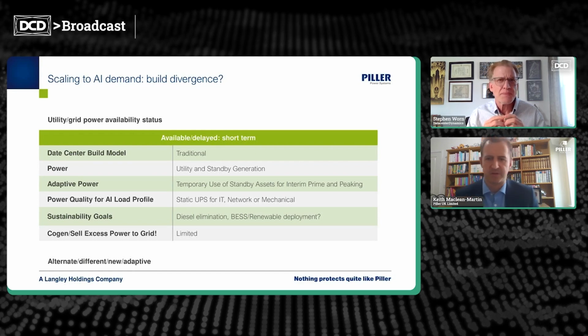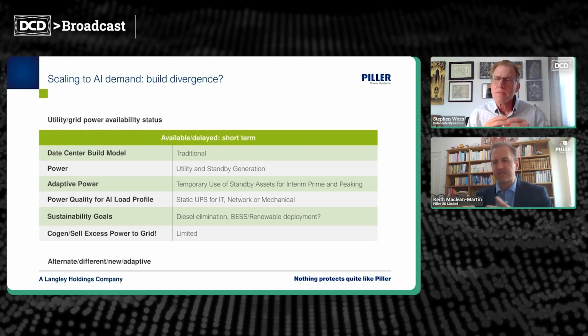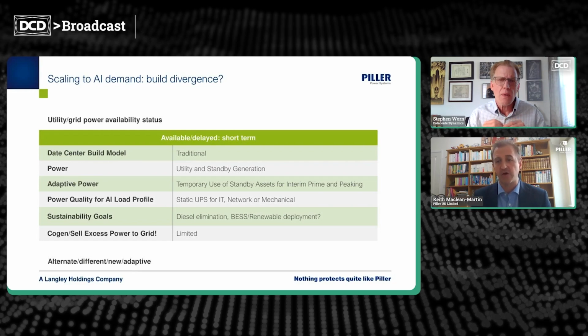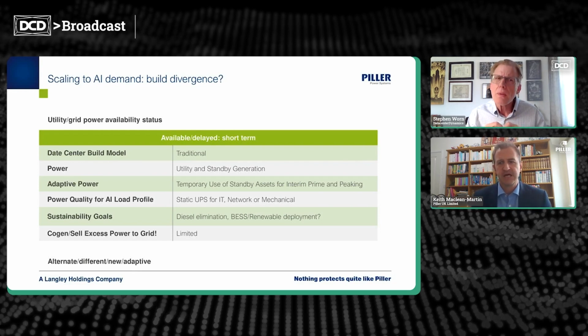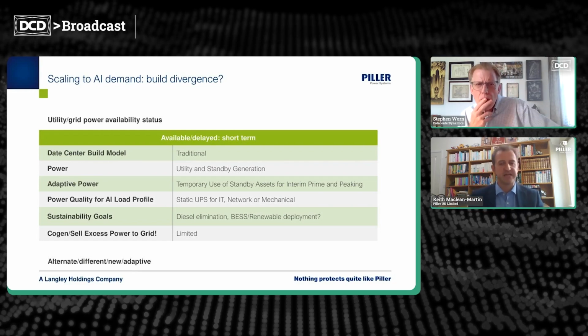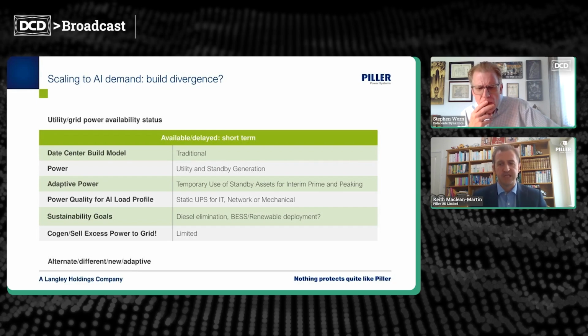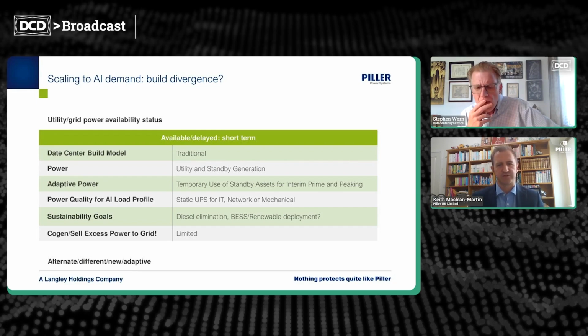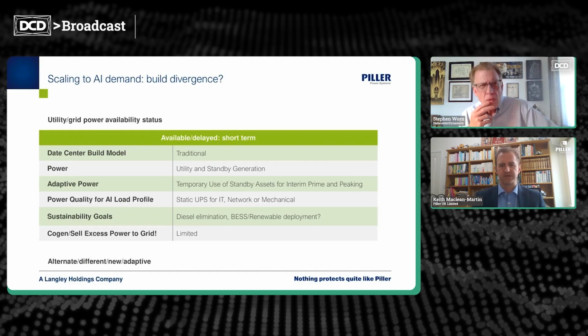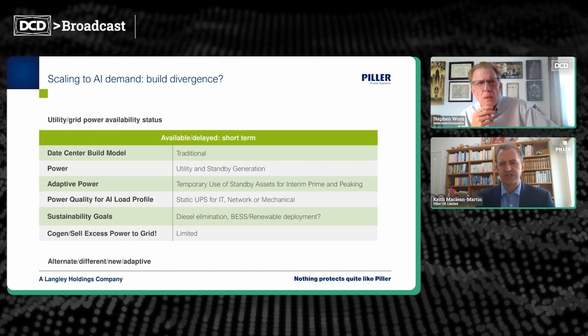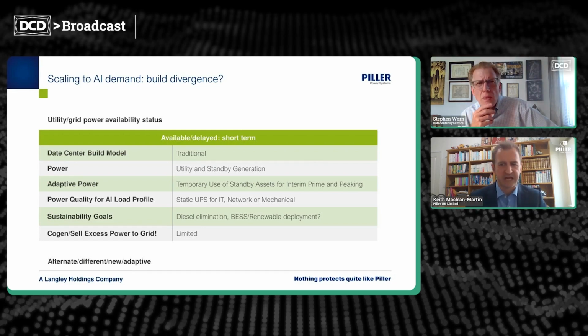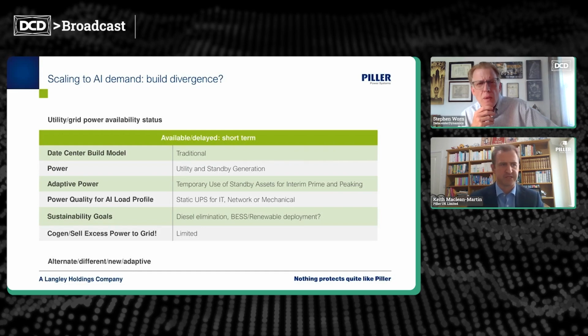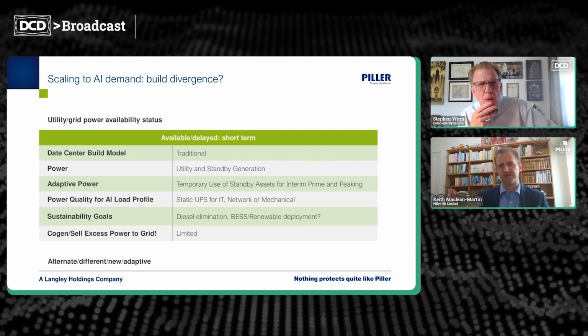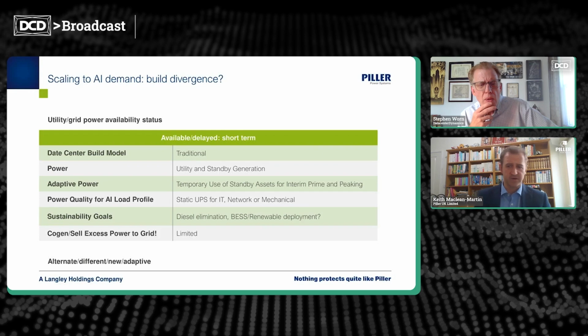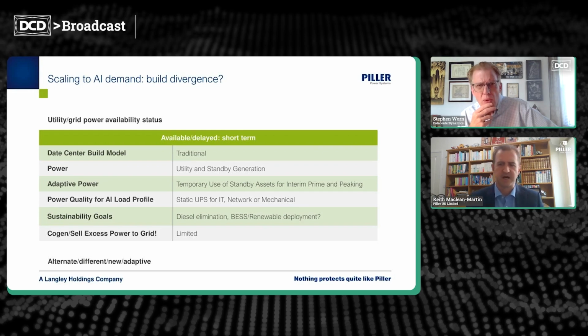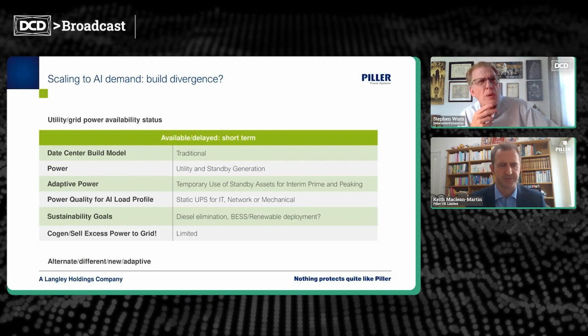So we now have a paradigm shift. If prime power is now localized in the microgrid and not from the utility supply, then the power quality, the availability, and the resilience of that power is more of a known and guaranteed source. It's all under the operator's control. So traditional UPS systems were deployed to protect loads from utility power quality disturbances and bridge the time for the standby generators to take over by bridging with the energy storage.